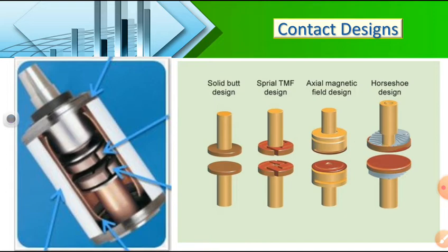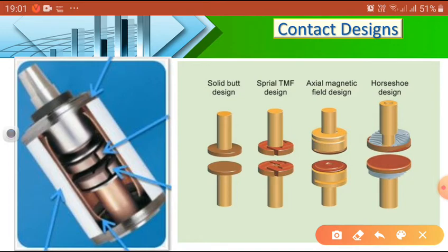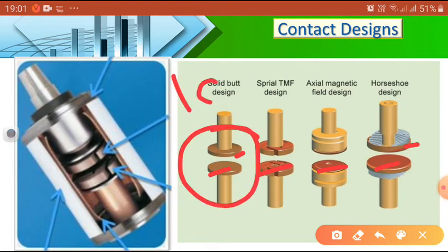So what have we seen? We have seen these rods, male and female, whose contact areas are eroding and evaporating. Even then, we can use this type of breaker for nearly 10,000 operations. So you can see how little maintenance this system needs.